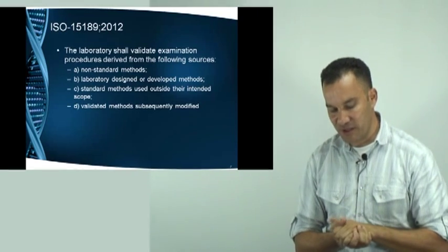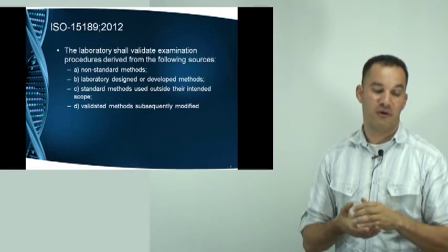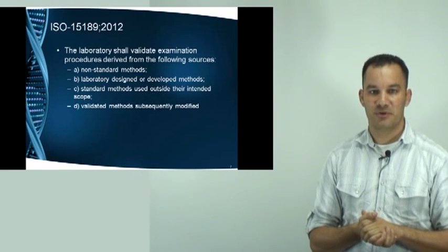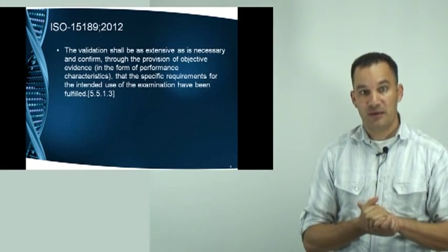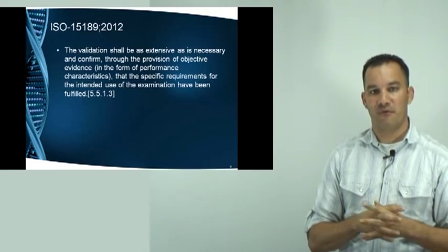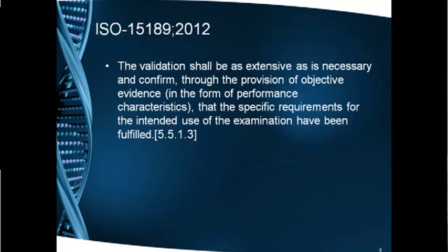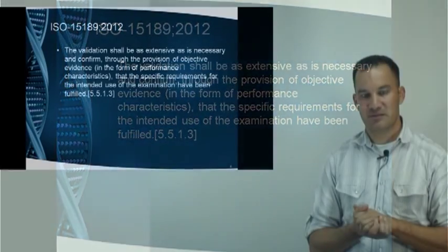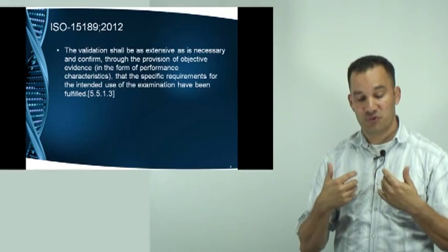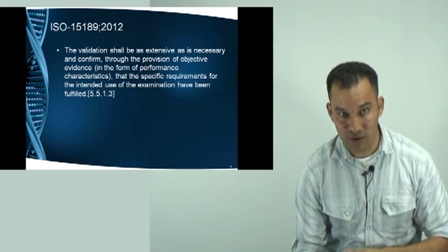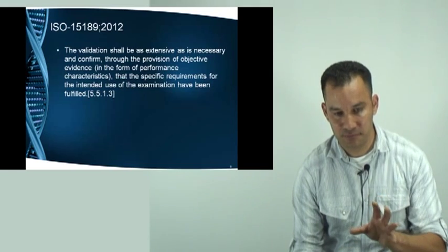Obviously, if we have validated a method and afterwards modify it, we have to re-validate or pay attention to that change. The following guidance says that we have to examine specific requirements for the intended use and perform experiments extensive enough to provide objective evidence — demonstrating all of the areas I am going to show you now.